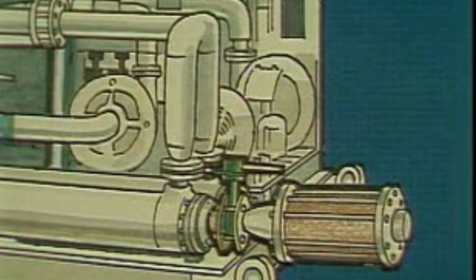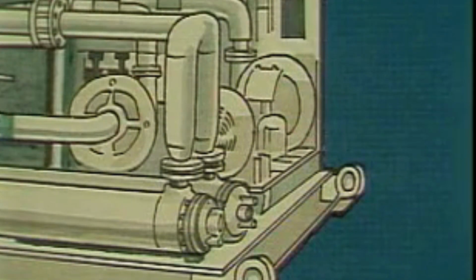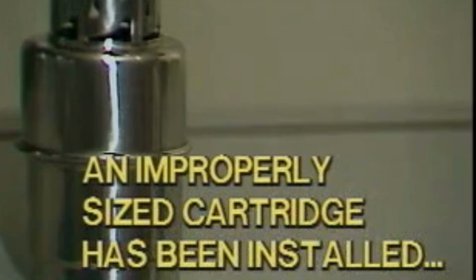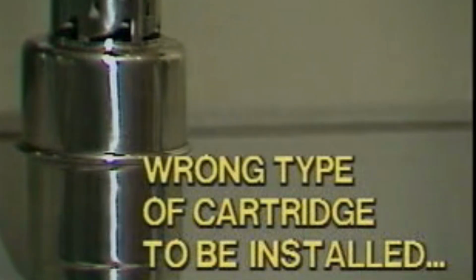Now, some of you may have not known what the flow controllers were used for. In more than one case, these flow controllers have been removed from the system. Since most people don't understand the flow controllers, they believe that they're not working or find them completely destroyed due to improper selection. For instance, freshwater valves used on a saltwater application. Actually, there are several things that could go wrong with the valves. First is that an improperly sized cartridge has been installed. Naturally, this could restrict or increase the flow more than you would want. The other problem that can occur is the wrong type of cartridge being installed.